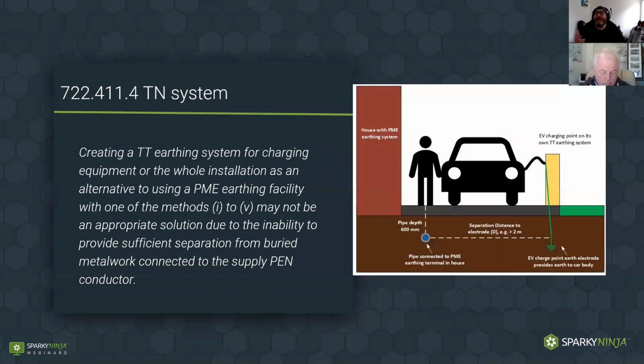Now, I mentioned earlier on about TT earthing, and this is a note that's right at the end of the TN system, the TN protection. And it says, creating a TT earthing system for charging equipment or the whole installation as an alternative to using the PME in one of the methods given just now in 1 to 5, may not be an appropriate solution due to the inability to provide sufficient separation from buried metalwork connected to the supply PEN conductor. So if I've got cables and pipes under the ground and I've got a PME, the electrodes in that PME are obviously creating a lot of common reference to the surrounding groundwork. If I then strike an electrode in close proximity to any of that reference, if the PME goes down and obviously the earth around becomes the reference for what would have been the neutral, then there may be a close proximity to my installed electrode that I might start to pick up that increased voltage potential again.